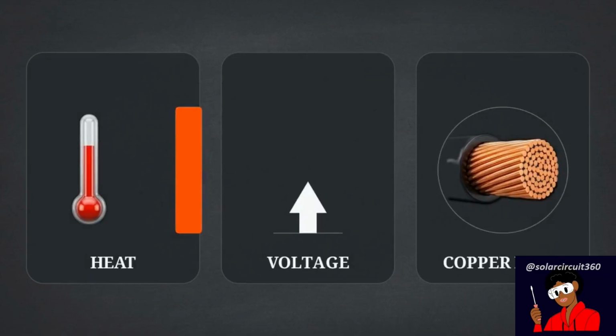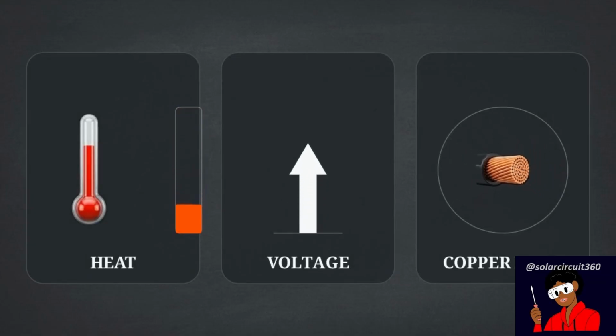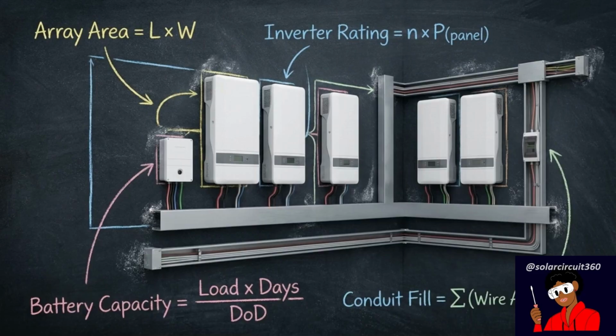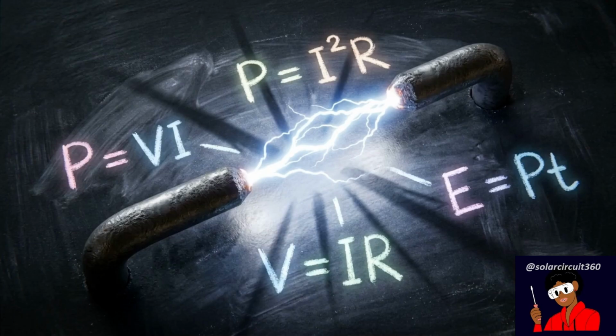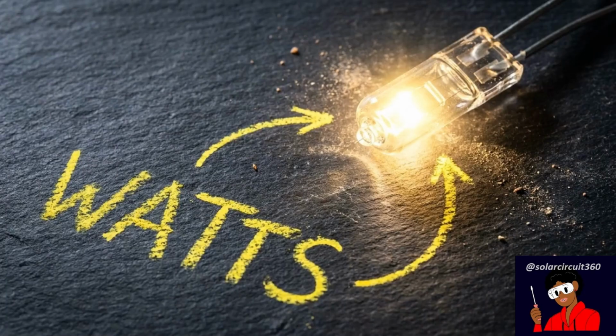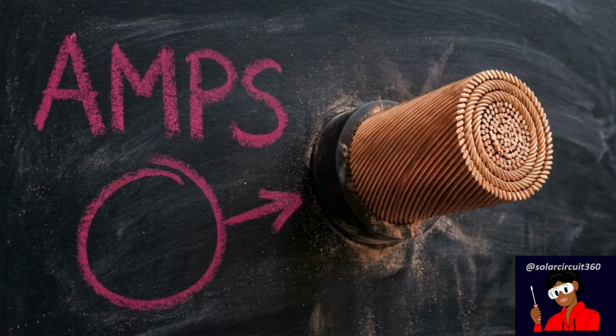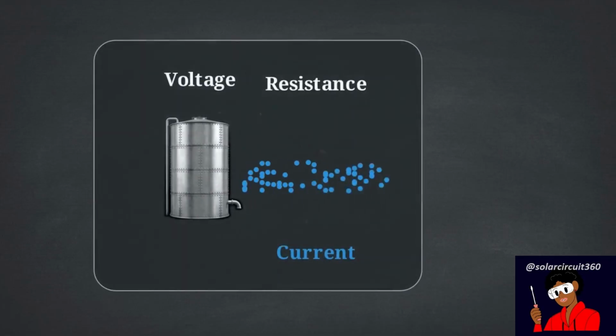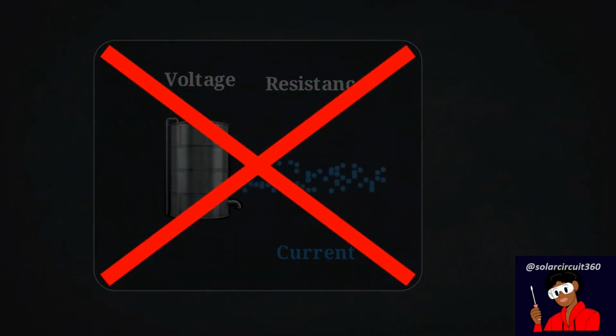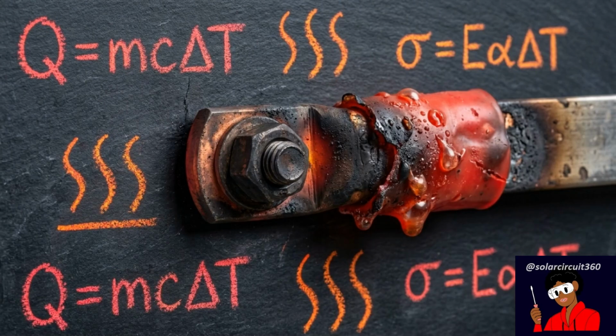We need to prove exactly how scaling up the system voltage alters the geometric scaling of both heat generation and copper mass. Transitioning to 48 volts keeps the physical demands of energy transfer within manageable limits, even as total power requirements grow. We start with the three bedrock variables of electrical power: the total watts, the system volts, and the flowing amps. We can discard the simplified tutorials that explain this using water flowing through pipes. In heavy-duty power systems, those analogies fail to communicate the real danger of thermal stress.